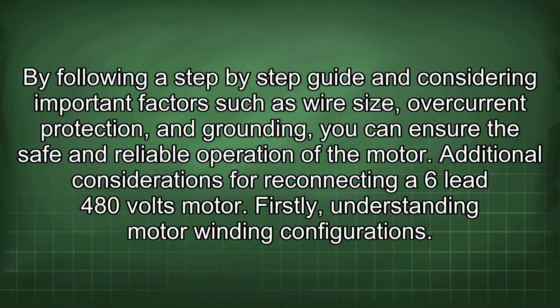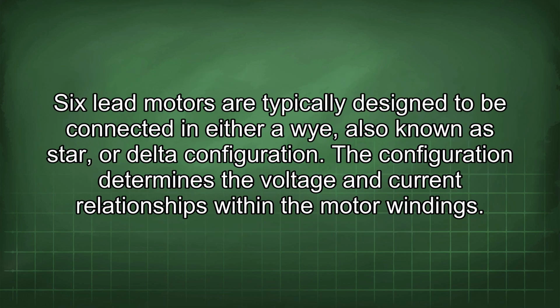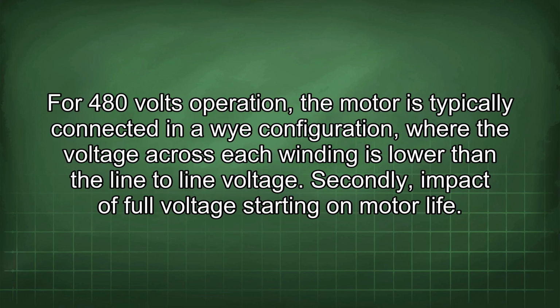Additional considerations for reconnecting a 6-lead 480 volts motor. Firstly, understanding motor winding configurations. 6-lead motors are typically designed to be connected in either a Y, also known as star, or delta configuration. The configuration determines the voltage and current relationships within the motor windings. For 480 volts operation, the motor is typically connected in a Y configuration, where the voltage across each winding is lower than the line-to-line voltage.